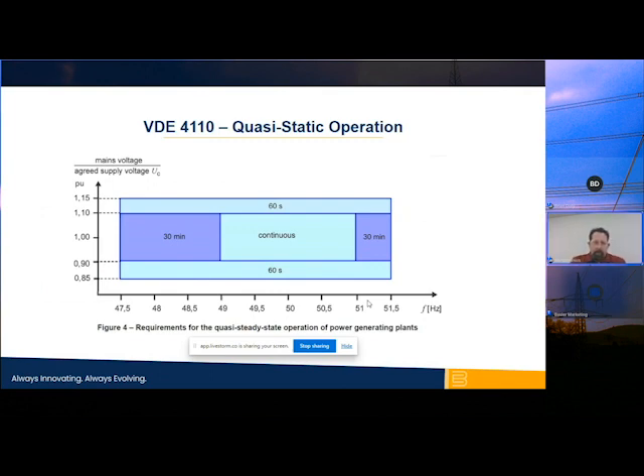So this is a graph showing quasi-static operation, and this is from the VDE 4110 code, which is a European German grid code. It shows where we want our machine to operate. If you look in the middle here, if I can pull up my cursor, you can see this is continuous operation. We're looking at voltage in per unit on the left, and frequency on the bottom. This particular machine's nominal frequency would be 50 hertz. This diagram tells us where we want this machine to operate and where the voltage regulator or the machine itself needs to be connected or disconnected.